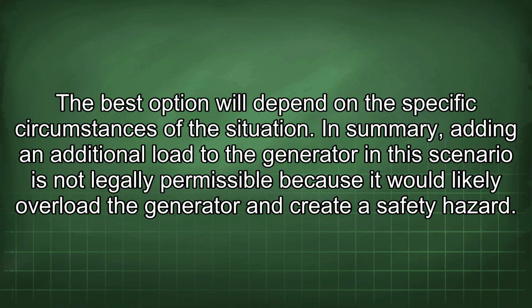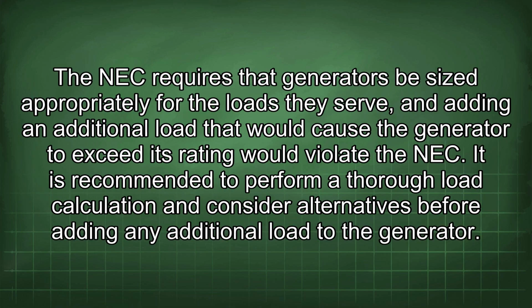In summary, adding an additional load to the generator in this scenario is not legally permissible because it would likely overload the generator and create a safety hazard. The NEC requires that generators be sized appropriately for the loads they serve, and adding an additional load that would cause the generator to exceed its rating would violate the NEC. It is recommended to perform a thorough load calculation and consider alternatives before adding any additional load to the generator.